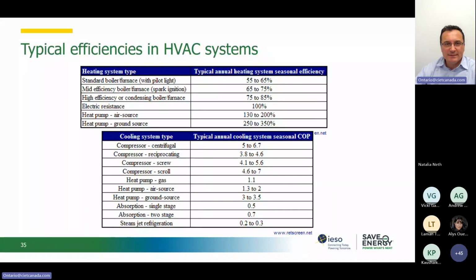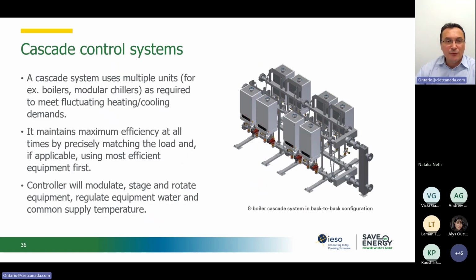And I mentioned that we don't need to invest always. I mean, if we can, perfect, but we don't need to invest in high efficiency heat pump systems for the entire load of our system, if we think that our system is going to operate for a limited number of hours. So what we actually look for is to optimize how we use our resources by having in the base load, whatever is running the most time, the most efficient equipment, and then stacking up equipment that's less efficient, but costing less. It's easier to maintain. It lasts longer, maybe. And it does use more energy, but it is using that energy for a low amount of time during the year. So that's where we can use this cascade control. So we try to prioritize.